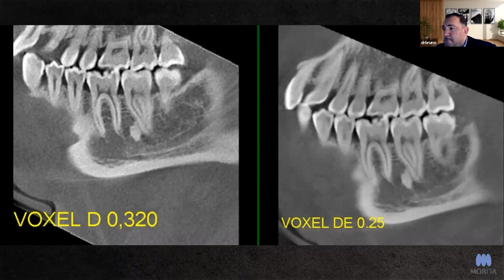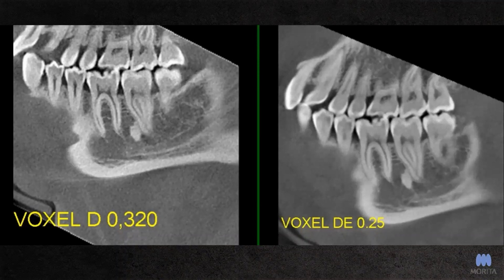Is that correct, Mr. Sliman? Yeah, essentially. I mean, the default resolution can be changed as a setting of the driver. So in the user manual, you'll see how to get access to the driver settings. And like Dr. Azevedo said, we don't normally recommend changing the resolution or the reconstruction filters, but in that same area, you do have the ability to change the default resolution. Now, of course, there are limits to that. We go down to 0.25 on this larger volume. You can't really go much lower.